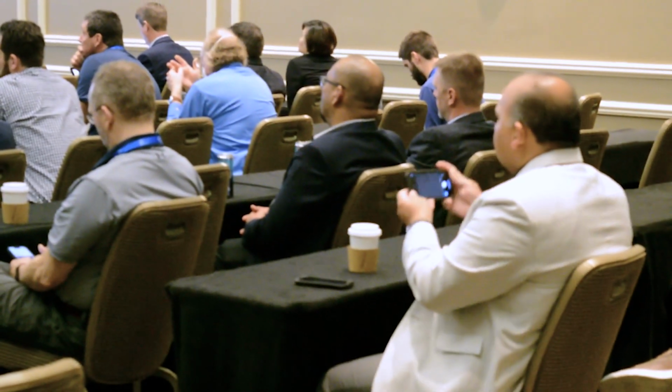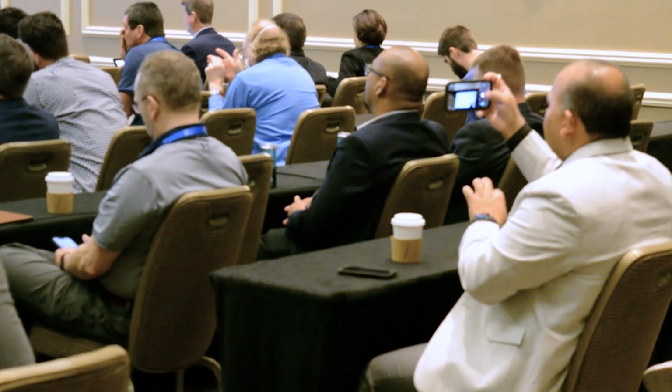Sent it out, had the pump torn apart, took a look, and on the inside it was all galled up and about ready to fall apart. We were able to use that technology now where we can create predictions on this. We can tell about 2 months before that pump's gonna go bad, that it's gonna go bad.